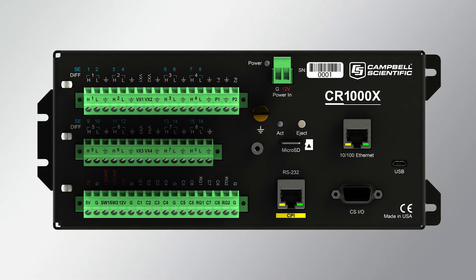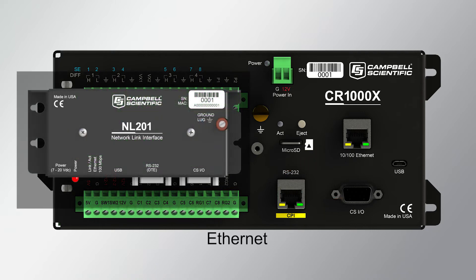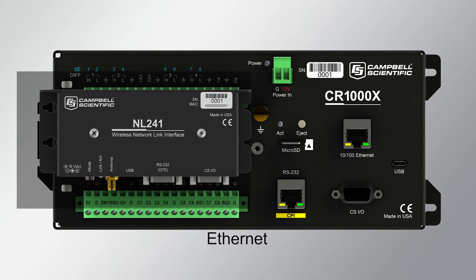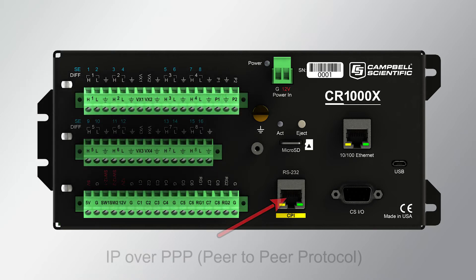Data loggers can support multiple IP interfaces, not just Ethernet. Each interface will have its own unique IP address, subnet mask, and gateway address. For example, on the CR1000X, IP interfaces include an Ethernet port and a CSIO port, which can connect to an external Ethernet interface such as an NL201 or NL241 wireless Wi-Fi link. In addition, IP over PPP, peer-to-peer protocol, is available with a CPI to RS-232 adapter or with any of the data logger's TX-RX pairs. Finally, the USB port supports RNDIS, or Ethernet over USB, for connection to a local network.